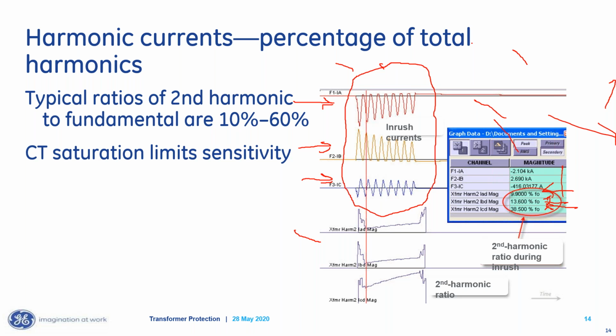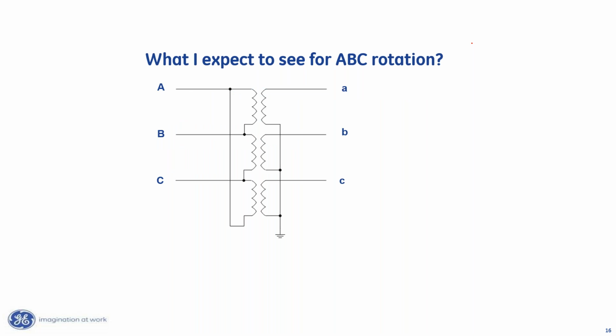On this particular one, let's see, 13 plus 38 is 50, and another 9 puts me at about 60. Divide that by 3, and I'm at 20%. So I'd restrain here on average. And so I think the average is a much better setting for the level of second harmonic.